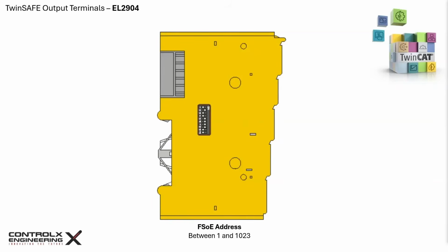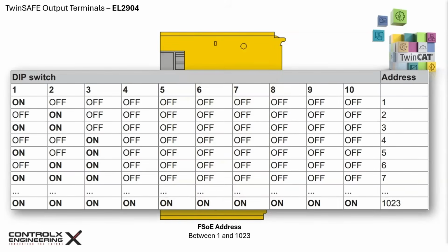The addresses have to be unique for each TwinSAFE terminal in a network and should not be repeated. Also, as I mentioned earlier, address 0 is not a valid address. This table shows these switch positions and the corresponding FSoE addresses.